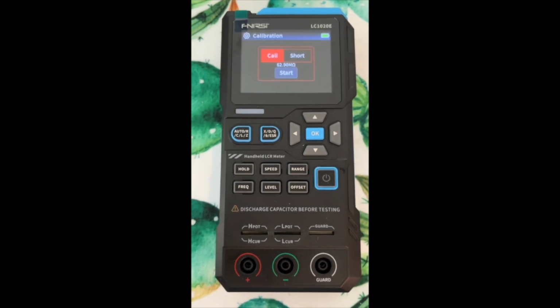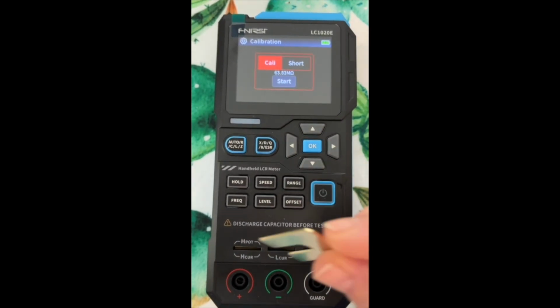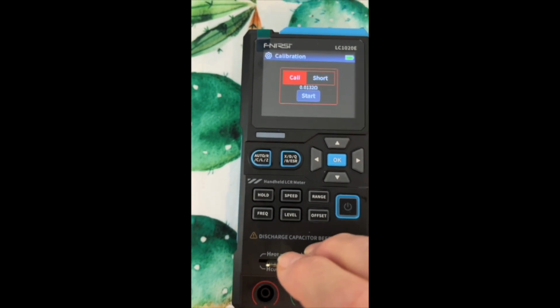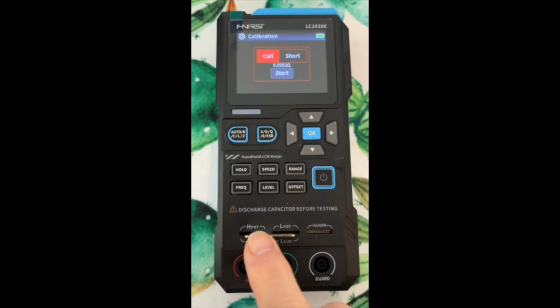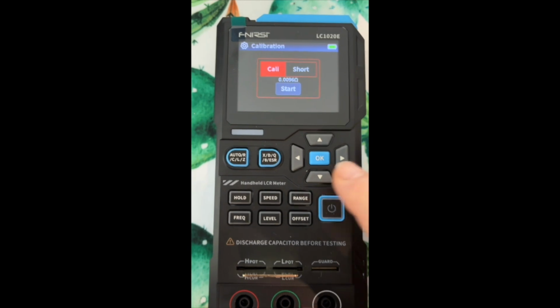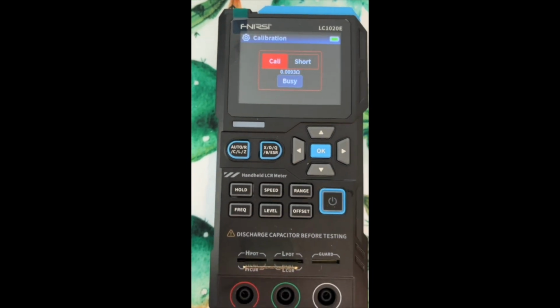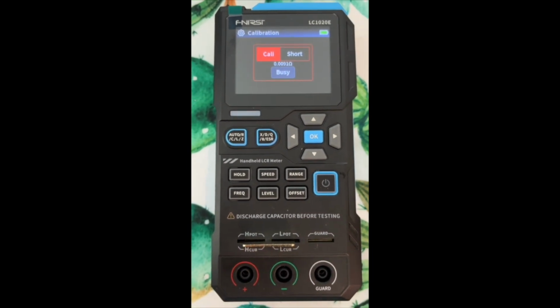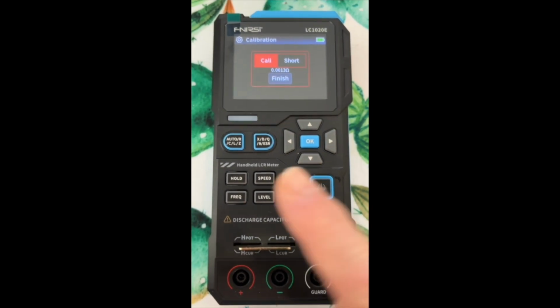Sure, the Kelvin leads on this are bad. We're going to do a quick test here. We're going to do a calibration with the shorting piece in here, and you'll see it will pass. And it passed with the shorting ring.